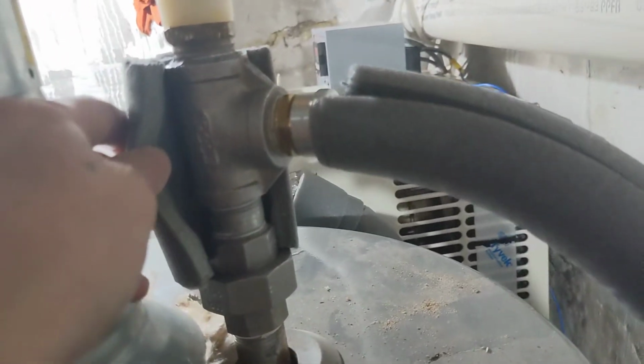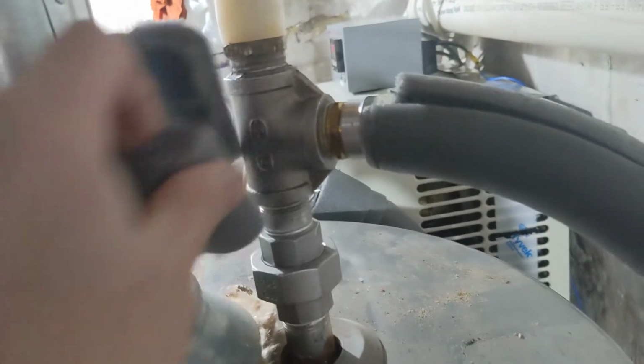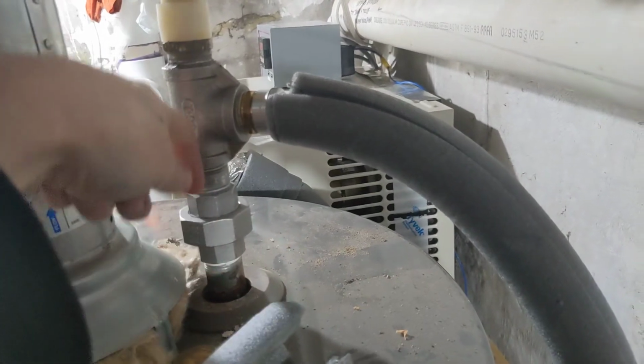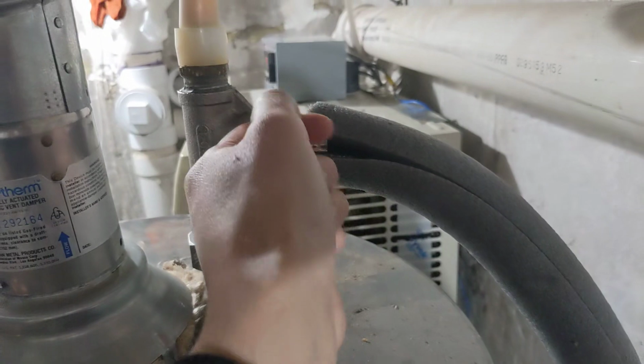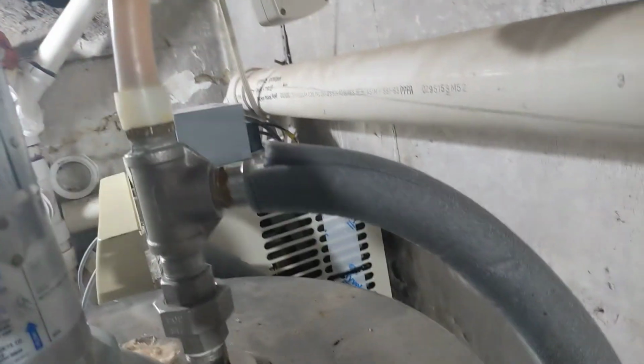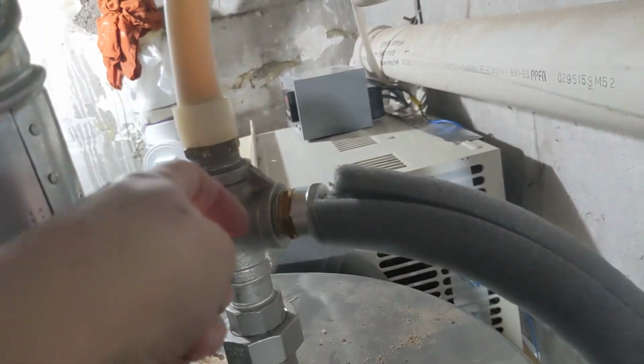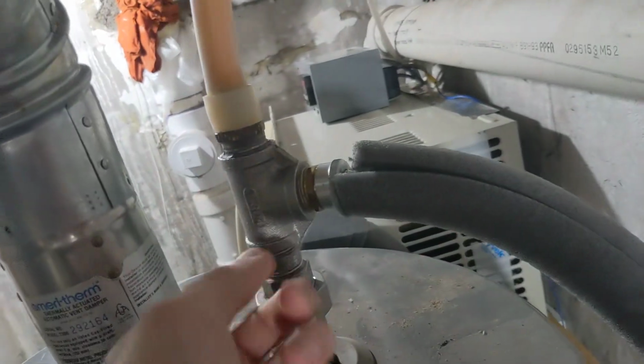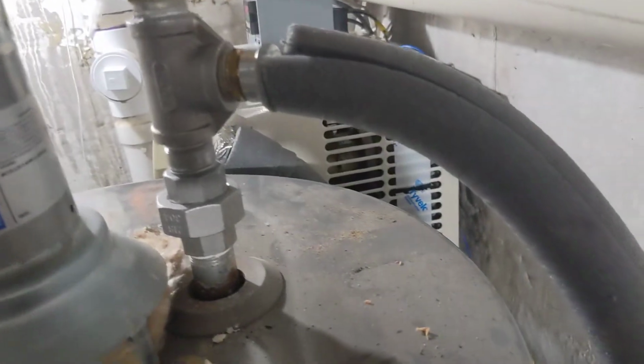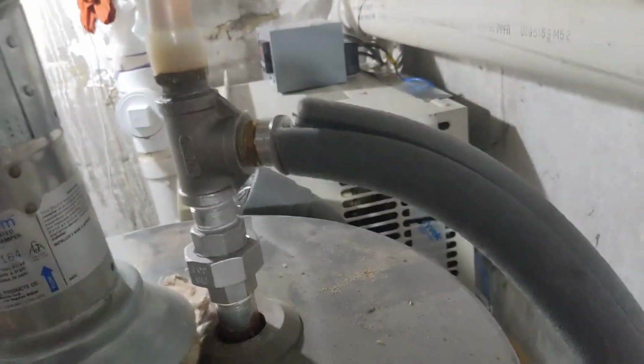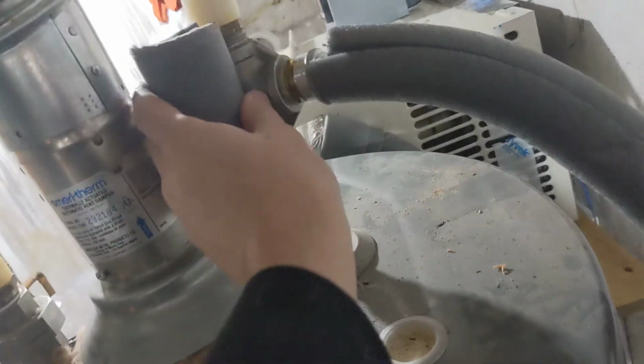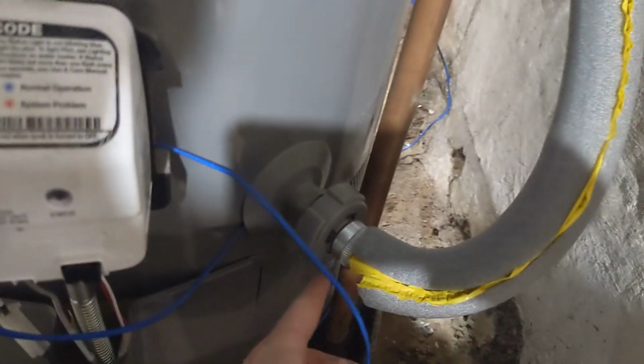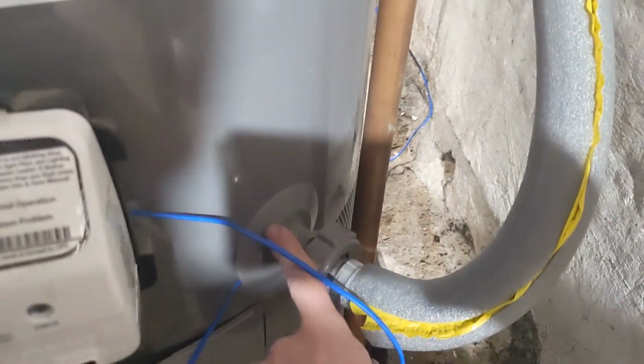So I reconfigured it so that the water going into the heat pump actually is drawn from the cold water inlet of the tank. So this line here brings the cold water into the water heater tank. Okay, that's cold water coming in. Normally it would just go straight down, but instead we are tapping it off and sending it to the heat pump. So if I'm in the shower or we're using water at the time, cold water will actually go to the heat pump instead of it sucking the hot water from the tank. Now if it's generating hot water and no water is being drawn from the tank, it just sucks the water from the dip tube up into the heat pump. And the water goes into the heat exchanger on the heat pump. It gets heated up and it gets pushed back into the tank through the bottom drain valve. So this is actually the heated water going back into the tank.